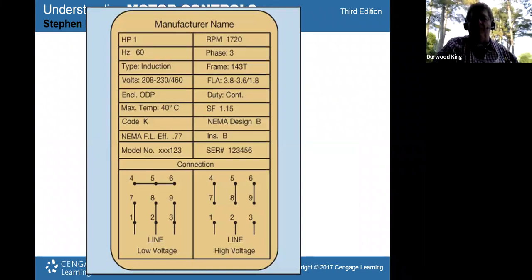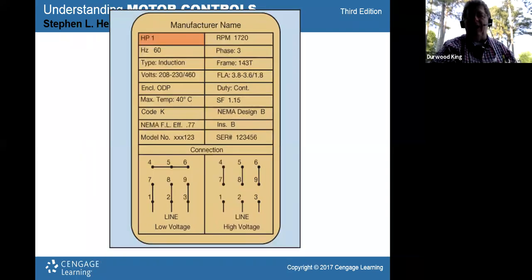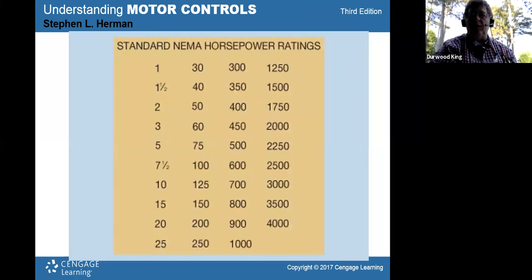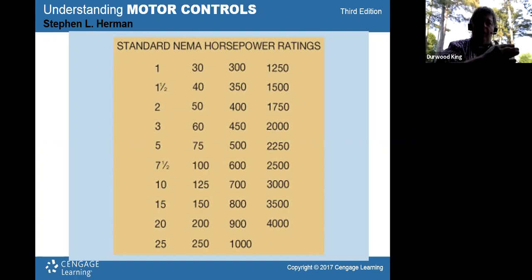So this is a picture of an example of a nameplate that has a lot of this information on there. The first thing they'll highlight is HP, that's horsepower. So that's a 1 horse. Of course, they go way higher. I've seen them as high as 150 horse, and they go even bigger than that. These are standard horsepower ratings that you can buy motors off the shelf. Starts out, there are fractional horsepower motors that go less than 1 horse, but this is just showing integral horsepower, whole numbers. So it starts out at 1 and it goes up to 4,000 horsepower. That'd be a whopper of a motor.